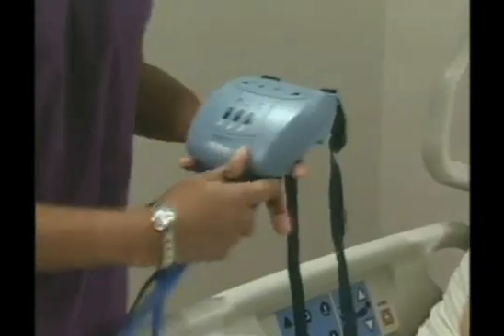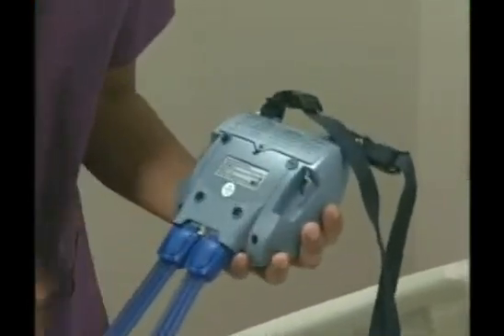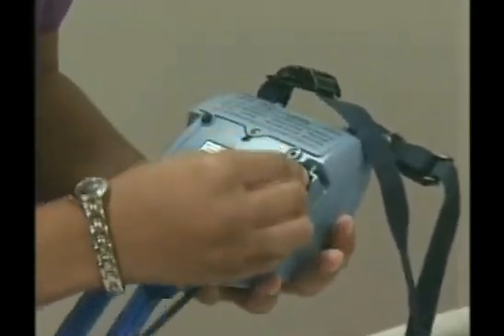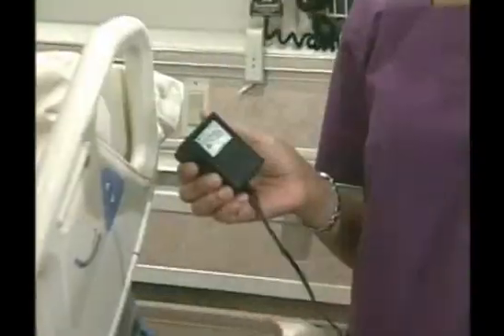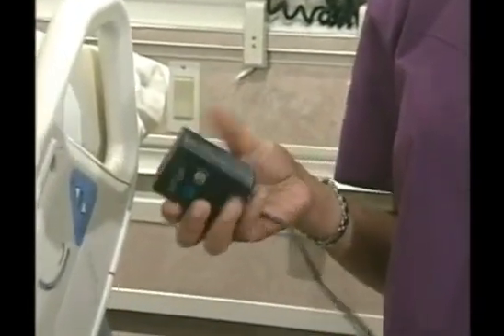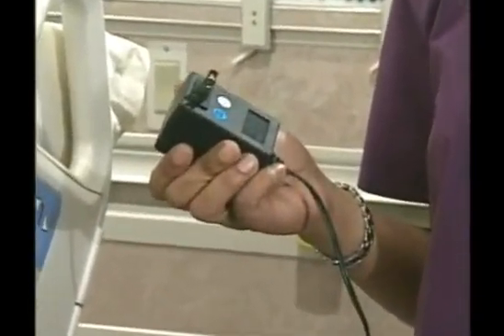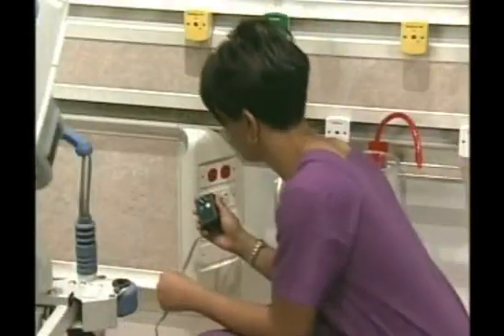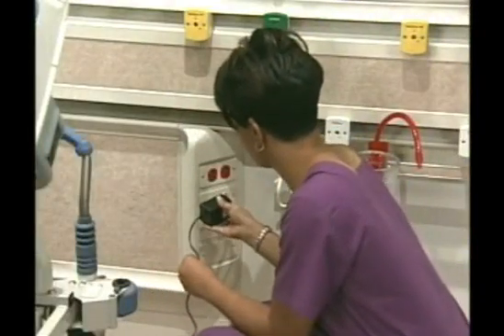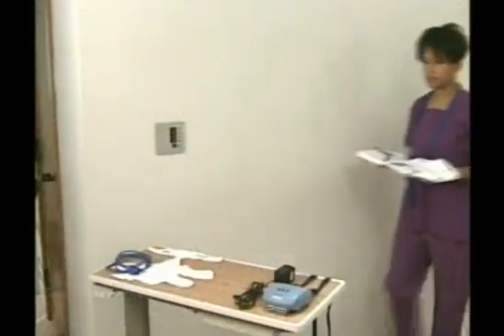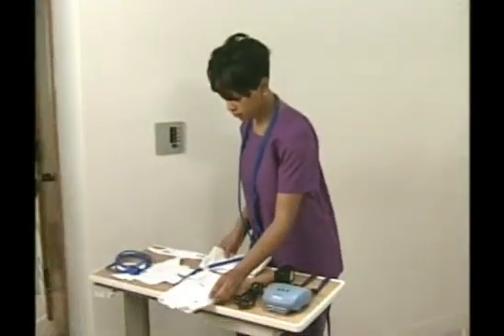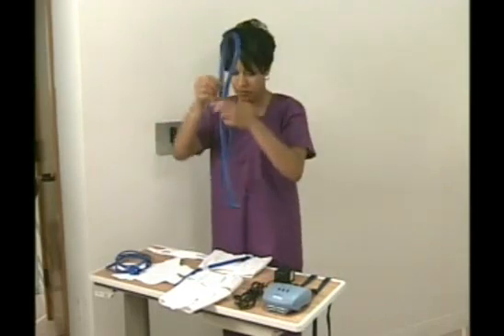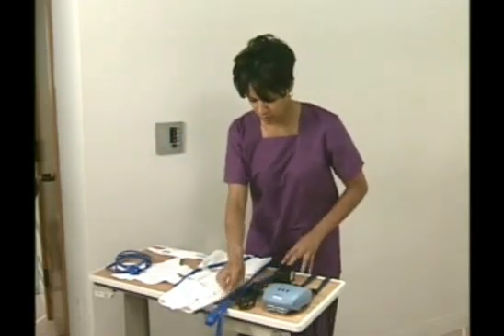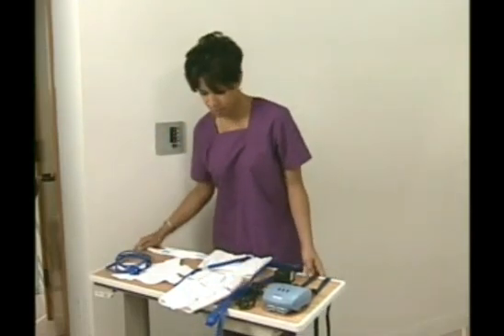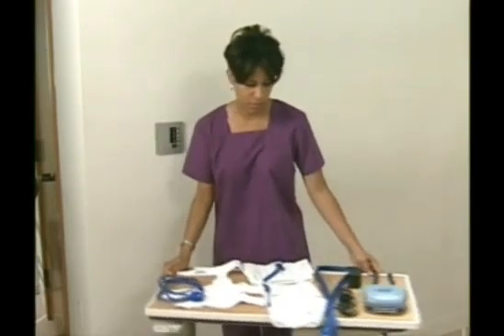To set up the ActiveCare DVT system, first connect the transformer to the DC power supply jack on the back of the device. Making sure that the transformer you are using has the appropriate plug for your electrical supply, connect it to the main power supply so that the rechargeable batteries can be charged. Assemble the desired combination of 1 or 2 sleeves and 1 or 2 lengths of extension tubing. Sleeves can be used in any combination while being controlled by a single device. Acceptable sleeve combinations are listed in the user manual.